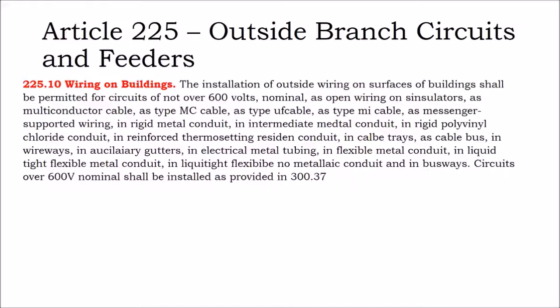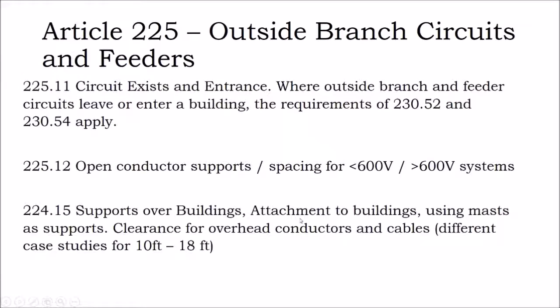Article 225, outside branch circuits and feeders, wiring on buildings. The installation of outside wiring on surfaces of buildings shall be permitted for circuits under 600 volts nominal. And then it lists different ways that you can have wiring on buildings. So you think, well, can I just go and staple a wire to the edge of the building? Code has a list of ways you can do it. You can have wire in metal conduit, wire in PVC conduit, wire in cable trays, and even certain cables that we'll get into in section 300 have protection and support built into them. And so if you see just a random cable running up the edge of a building, either it's the system ground, or it's a special cable that probably has a harder shell around the exterior of it.